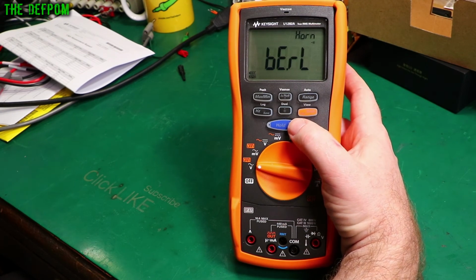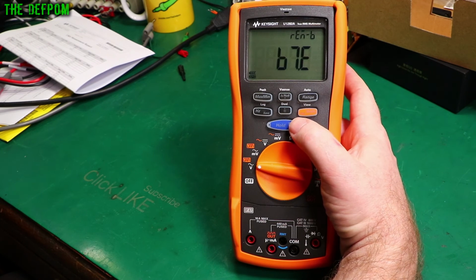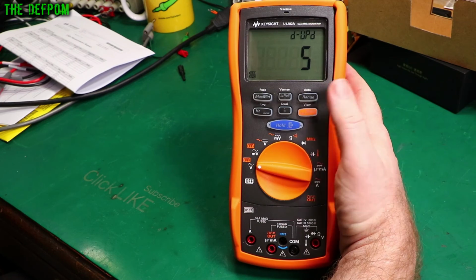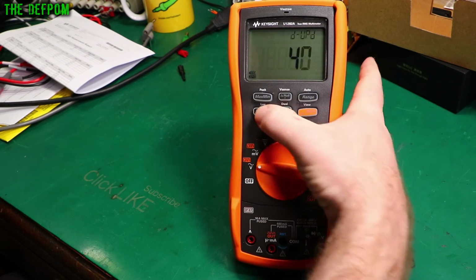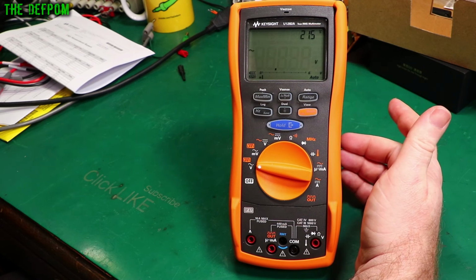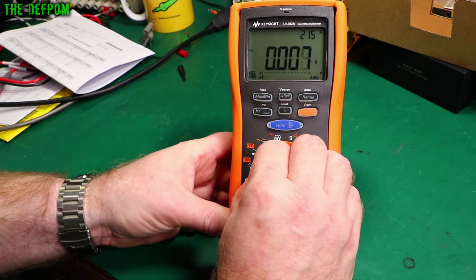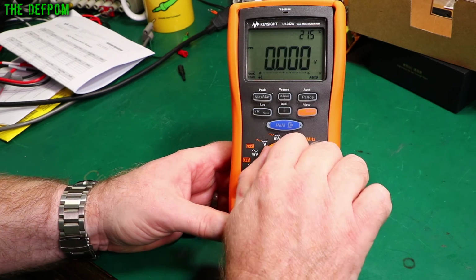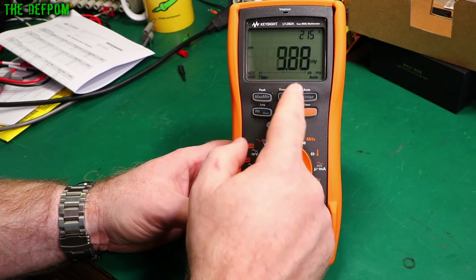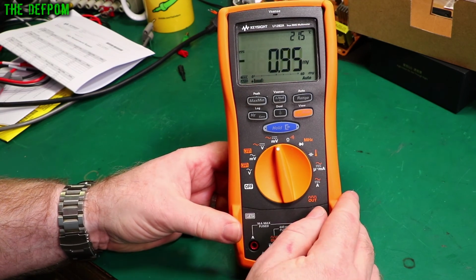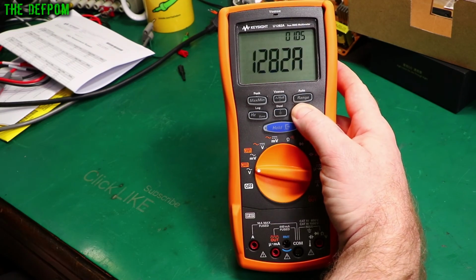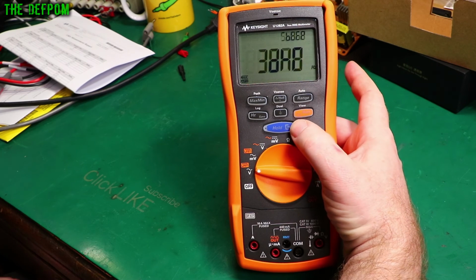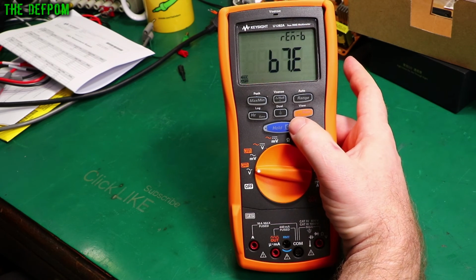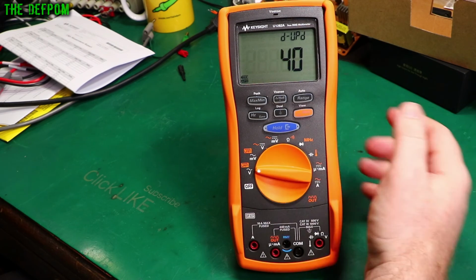Yeah, okay, anything else we need to do in here? Type short we want that, don't we? Horn, battery primary, reset no. Don't know what that was. Display high resolution. Display update is 5 times a second, which is fine because, like I said, if I go to 40 times a second I believe the resolution drops. Let's find out. So yeah, now we've got less digits going on here. We don't have the primary digit there. Yeah, but look at the update rate, that's pretty nice. Anyway, I think I want to keep it as high resolution. More digits is better. So you'll find it again. That's the update rate. So back to 5.